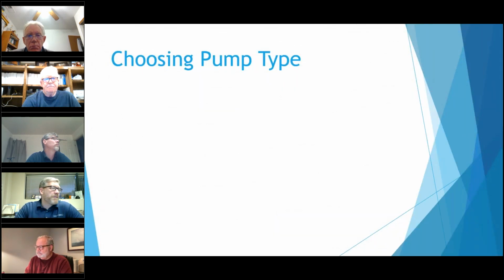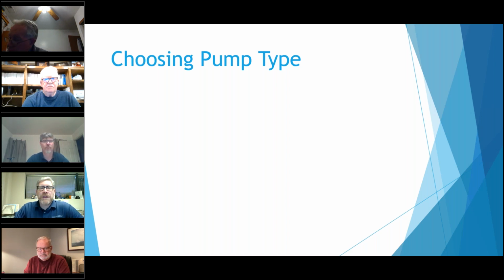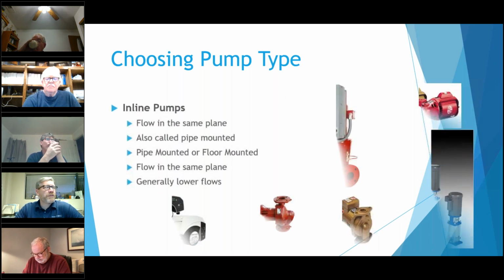So we were talking about before coming up with the GPM and the feet of head with the pumps, and sizing them and how they were sized. It's tough to get to that point sometimes, but once that's all determined, now you have to actually pick the pumps that you want to use. I'm going to go over a couple of the different styles of pumps first.